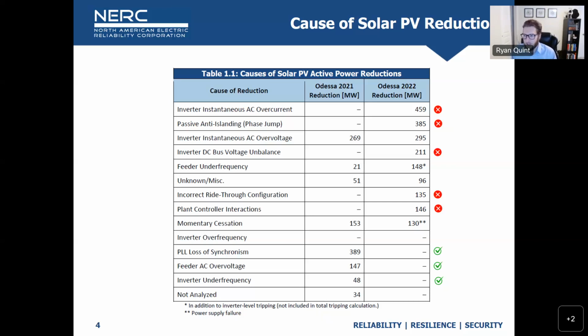My hunch is we'll need just as many, if not more, because it's going to require extremely detailed representation of that controller. And I want the model that's coming directly from the inverter manufacturer, not a generic model that's making broad assumptions of what the plant may or could or maybe is doing based on some fundamental expectation of what grid forming is. I want what's actually programmed in that device. So for that, I'm likely going to need a user-defined positive sequence model and an EMT model, and proof that they match each other.